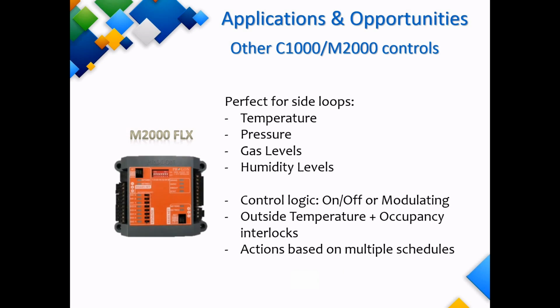Finally, we have the Flex.io, which is a little bit different from the other controllers in that it is not application specific. All the other controllers we have reviewed up until now had dedicated applications, and so all inputs and outputs were pre-configured for that application. The Flex.io is different in that you can configure it to control a variety of side loops.